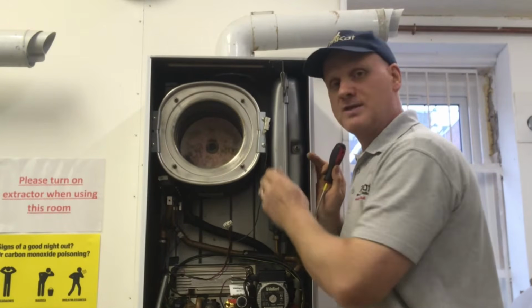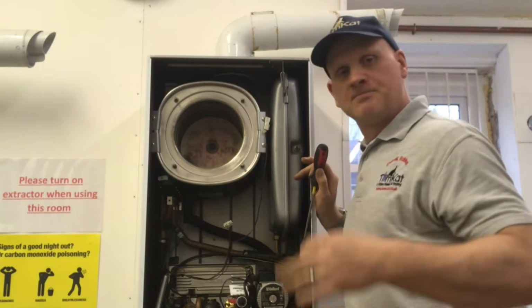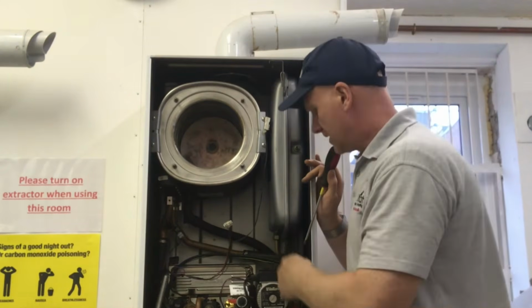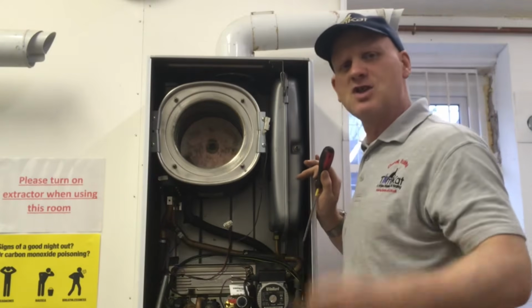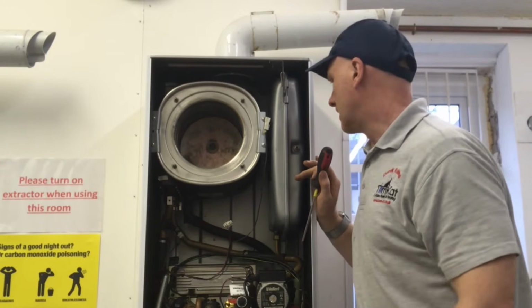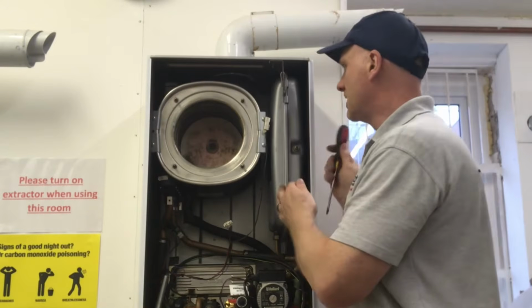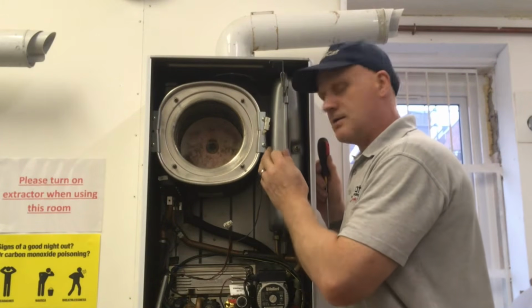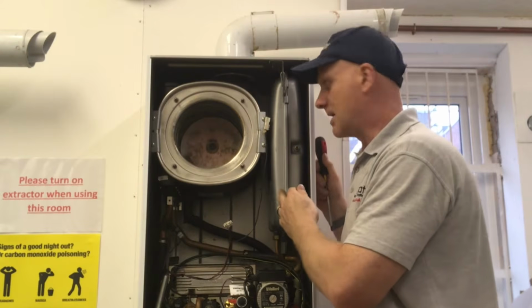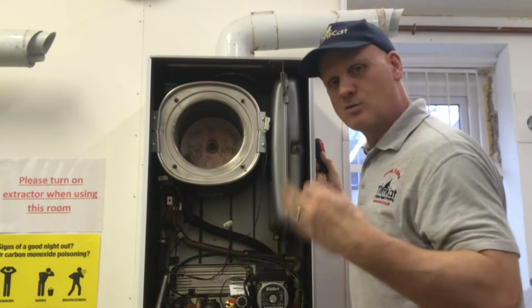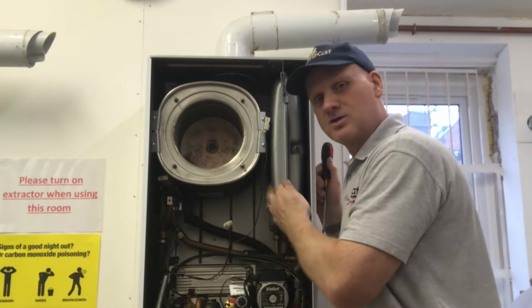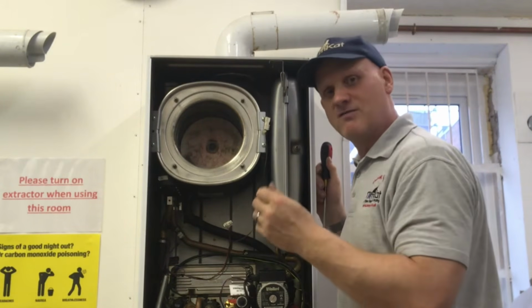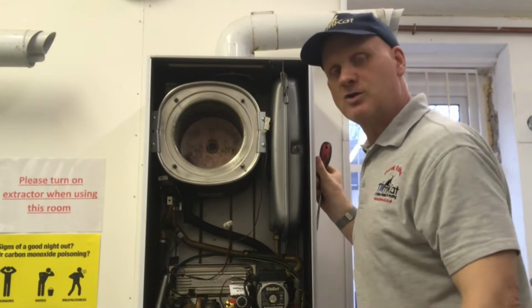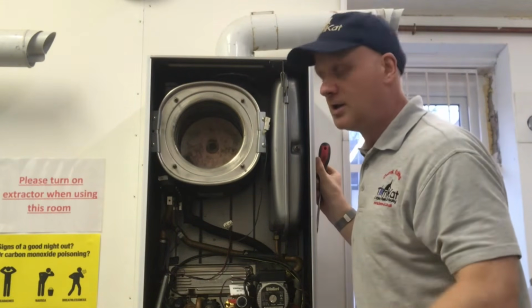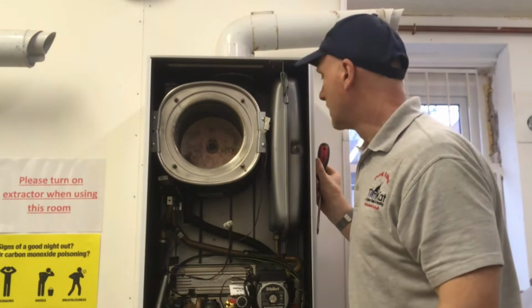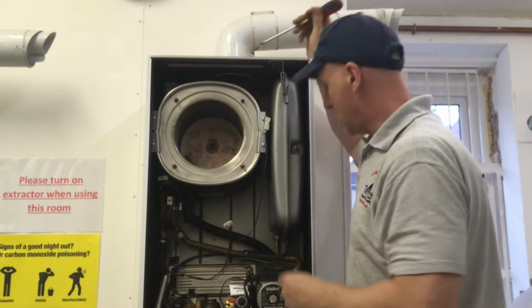Okay. Now, the major problem with this is if the diaphragm has gone inside, or it has lost its air, what would happen is the water would blow off on the pressure relief valve because there's no way of taking up any expansion. Okay. Now I'm going to show you how to take this out. The one thing you must be careful of is these will weigh an absolute ton when you take them out. Now, a litre of water weighs 1 kilogram. So these could be weighing up to 20-25 kilograms on some of them, so be very, very careful. That's why on unvented cylinders, if you go and do any repairs on that, the expansion vessel falls off the wall, because people don't realise they need to be secured. Now, all it is is 2 securing screws here and the nut here.